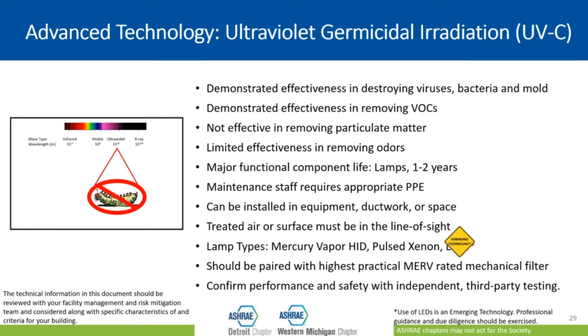Particular technology, UVGI, has been around for a very long time. It's very well documented. It's frequently used in hospitals and laboratories, municipal water treatment facilities. It is also used in schools and in commercial applications. And this is a very, very effective strategy for contaminant control. However, if you do intend to add this to your system, be aware that PPE is required for maintenance. Radiation causes sunburn and can damage eyes, and long-term exposure can contribute to other health challenges as well. So be aware of these things.